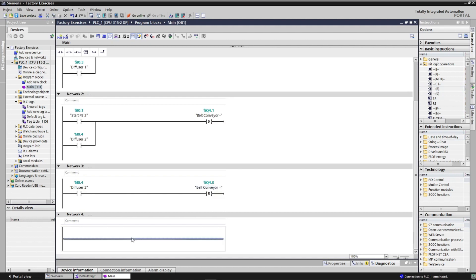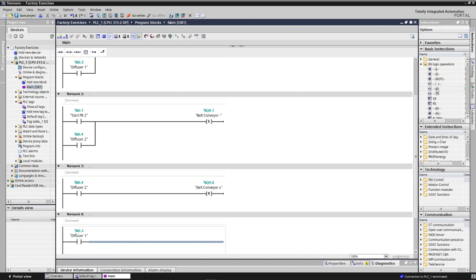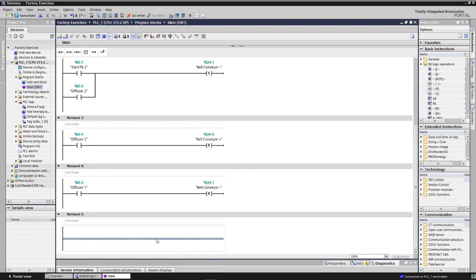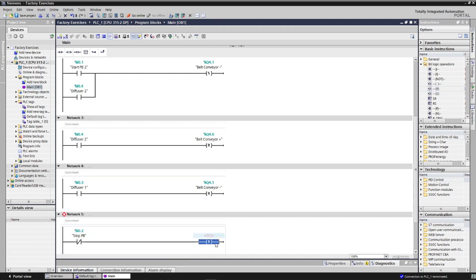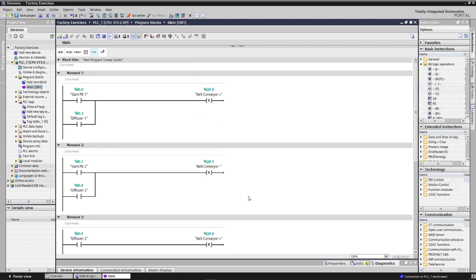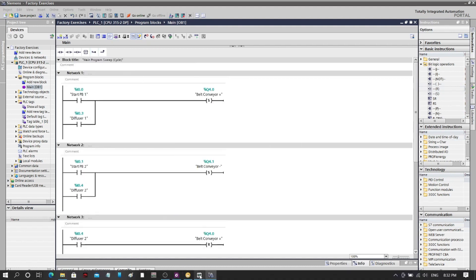Diffuser two will reset the belt conveyor positive forward direction. Meaning, when the box reaches diffuser two, the forward movement of the conveyor will reset or stop, and then diffuser two will energize the reverse direction movement. Same for diffuser one — it will reset the reverse direction movement. We will also add a normally closed contact for the stop pushbutton to stop both conveyor directions.